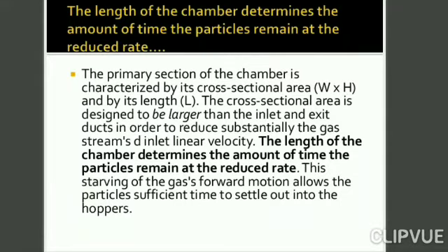The cross sectional area is designed to be larger than the inlet and exit ducts in order to reduce the gas stream velocity substantially. The gas stream's inlet linear velocity and the length of the chamber determine the amount of time the particles remain at the reduced rate.